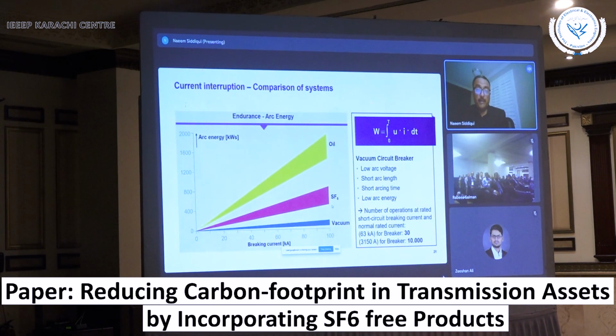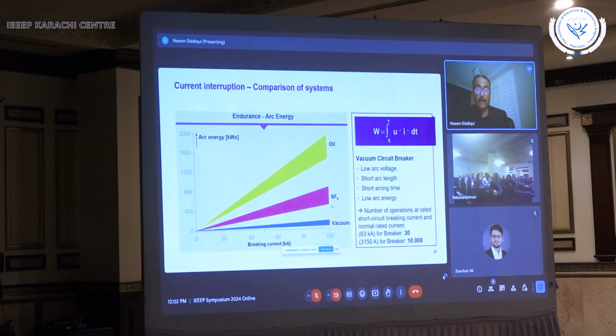Okay, this is the arc energy I was talking about. If your breaker is an oil breaker, SF6 breaker, or vacuum breaker, arc energy is very low in the vacuum system, and that is why the life of the contacts inside the vacuum for current interruption is very high. Normal SF6 breaker life is 25 to 30 years. Vacuum clean air breaker could easily be 50 to 60 years, so almost 2 times the life of the breaker you can have.